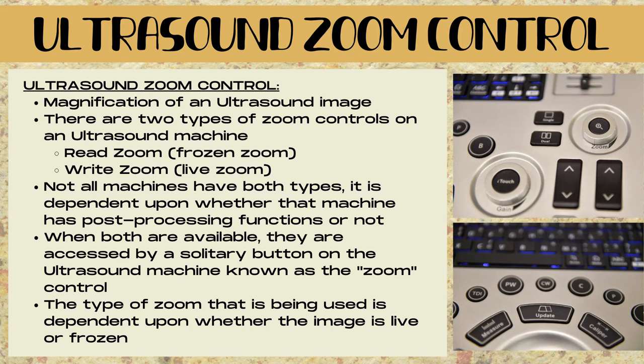Zoom is magnification of an ultrasound image, and there are two types of zoom controls on an ultrasound machine: read zoom, which is known as a frozen type of zoom, and write zoom, which is live zoom.